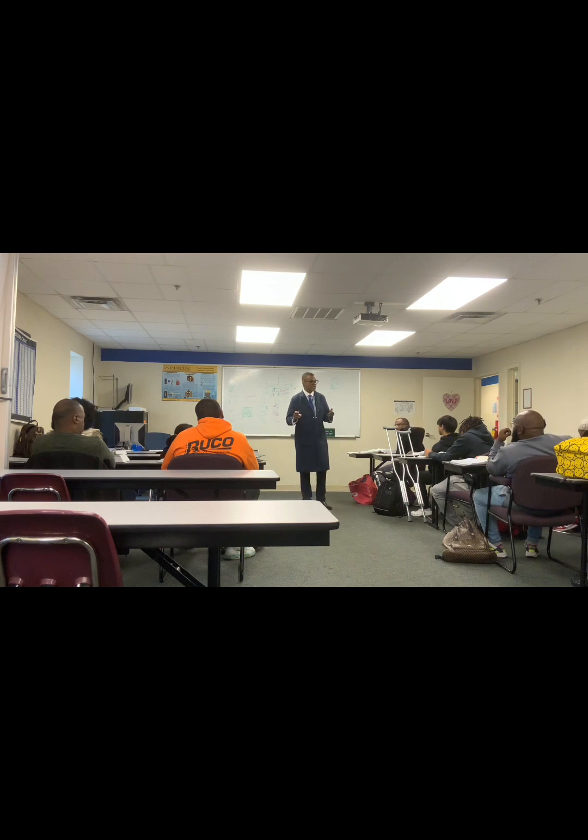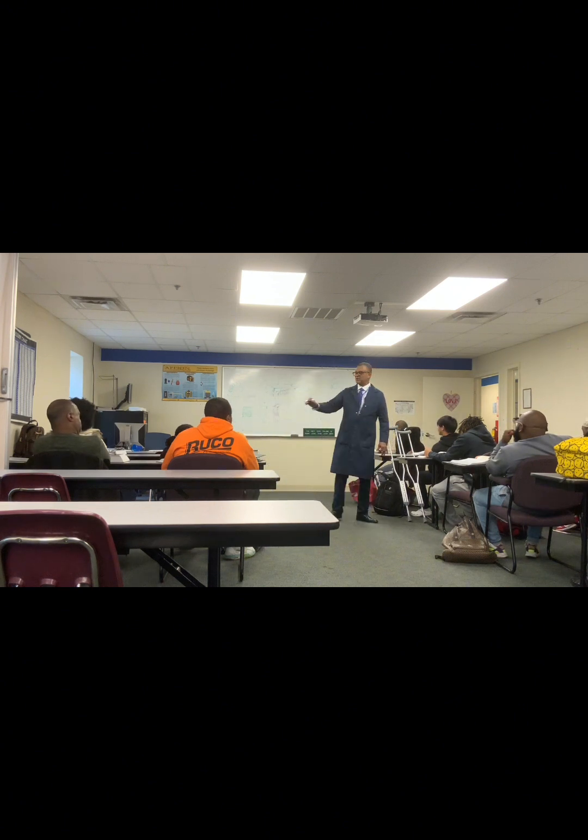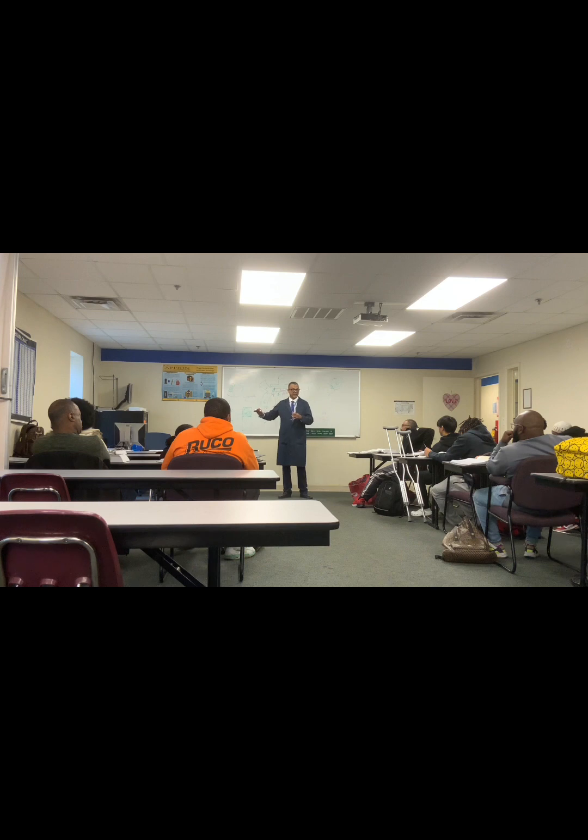Don't put a thermostat in the kitchen. It depends, all these new houses have this open format. Everything's open. I walk right here, I'm in the family room, I'm right here in the kitchen, I walk over here, I'm in the dining room, ain't no walls. So the stat needs to be over there, like in your little family room, away from the heat of the kitchen. But if it is, it is. It should be near the return as well. I don't know if you have a return down there, you should. You might check that.